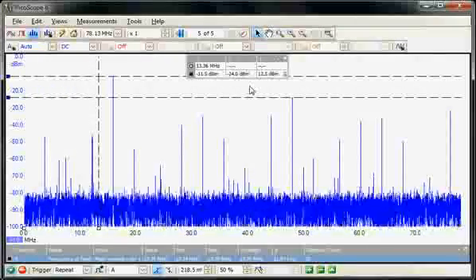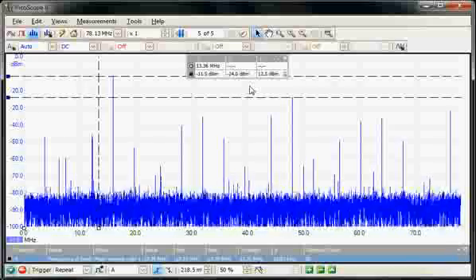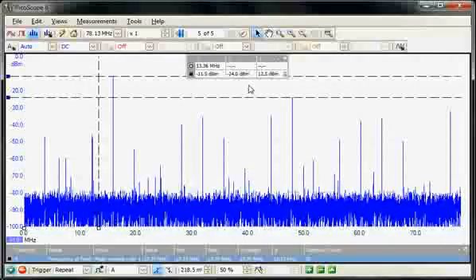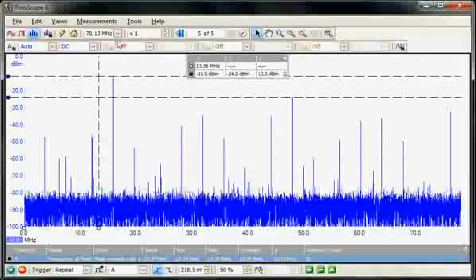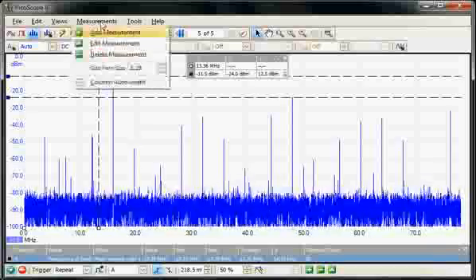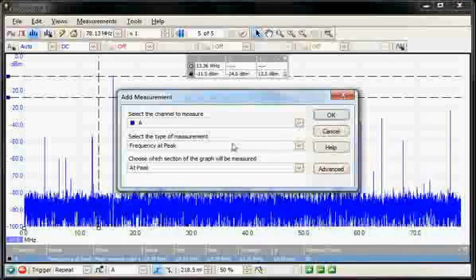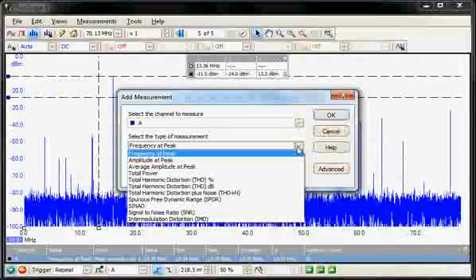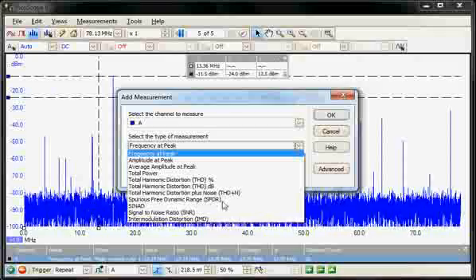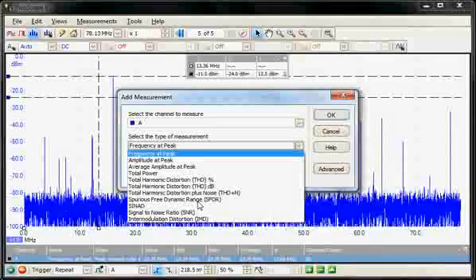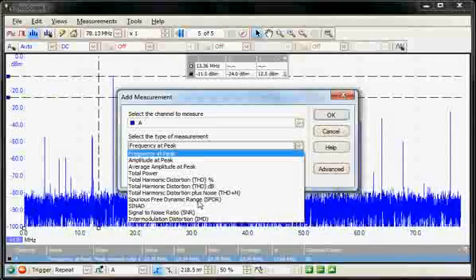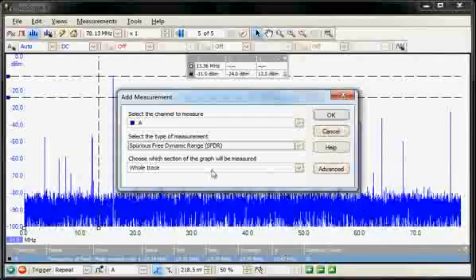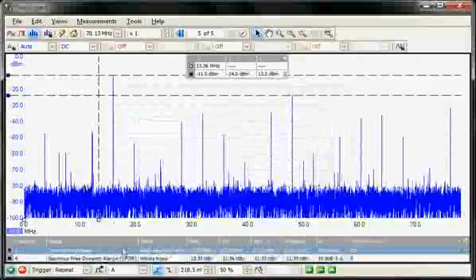It is possible again to use a measurement to measure this difference in amplitude directly. So again, we select the measurements. So here we see all the different measurements available. So we're going to select, for this second measurement, the spurious-free dynamic range. Select it across the whole trace and say OK.